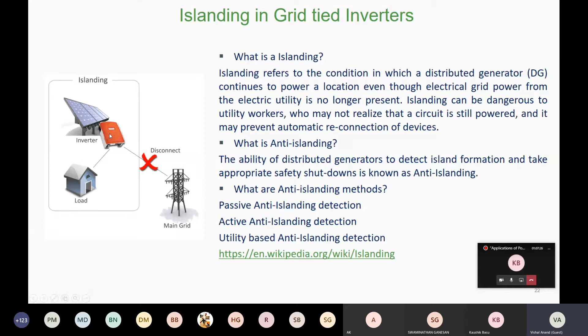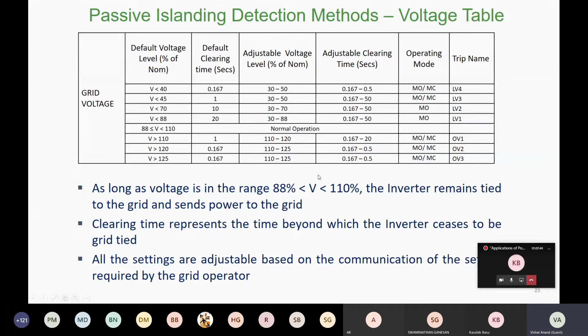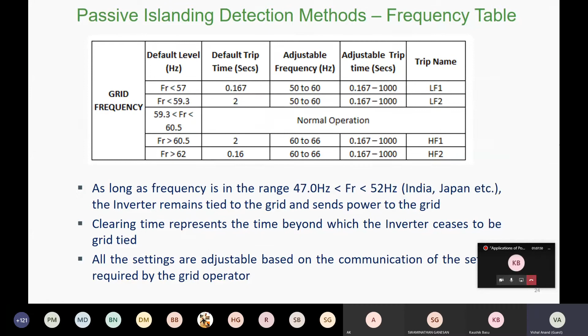There are different techniques available. One is called passive islanding detection, where we look at the voltage and frequency levels and then disconnect. This is a typical table given here for a grid. The clearing time is the time for which the inverter looks at the voltage and then disconnects. And all these settings must be adjustable. This is for the voltage, and we have a similar kind of table for the frequency, where we look at the frequency and disconnect.